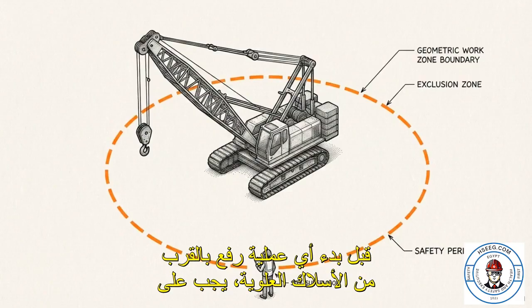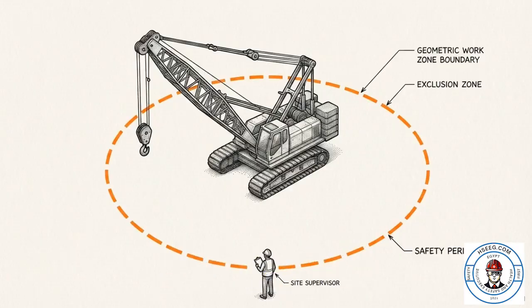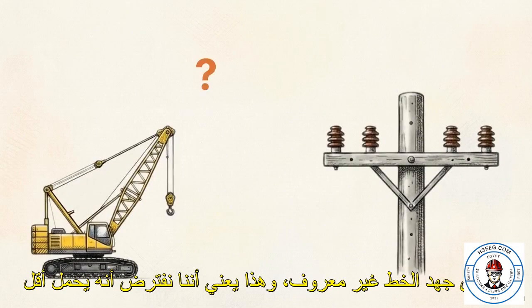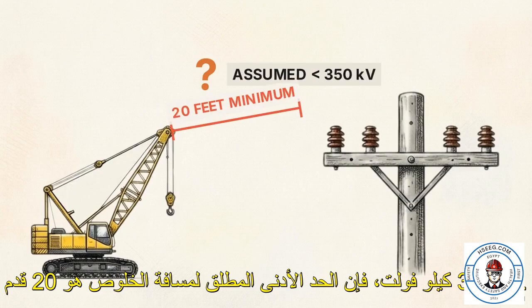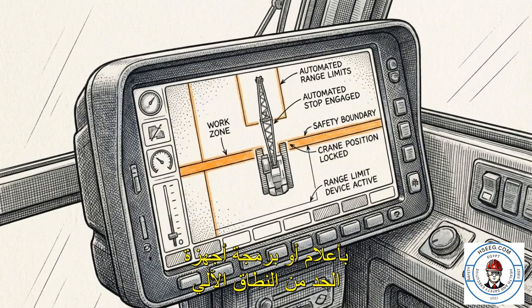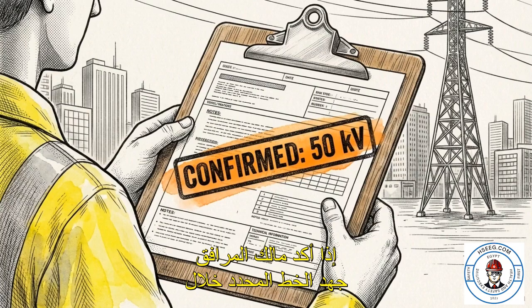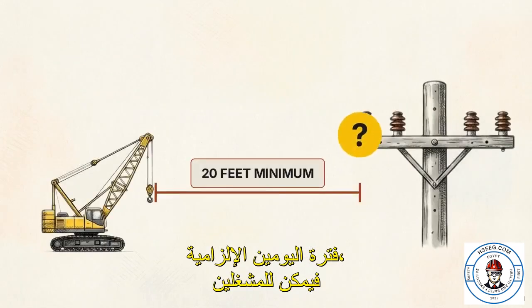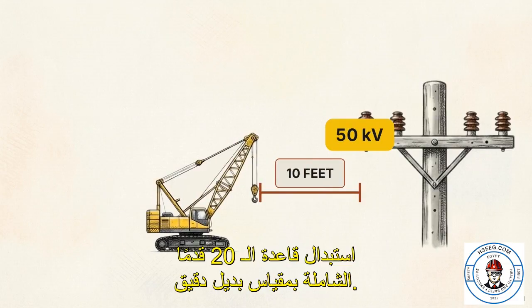Before any lift commences near overhead wires, the site controller must formally identify the equipment's maximum work zone. If the line's voltage is unknown, meaning we assume it carries under 350 kilovolts, the absolute minimum clearance distance is 20 feet. This boundary must be physical or programmed. Crews must erect elevated warning lines equipped with flags, or program the crane's automated range limit devices to prevent the boom from physically breaching that radius. If the utility owner confirms the specific line voltage within the mandated 2-day window, operators can replace the blanket 20-foot rule with a precise alternative metric.